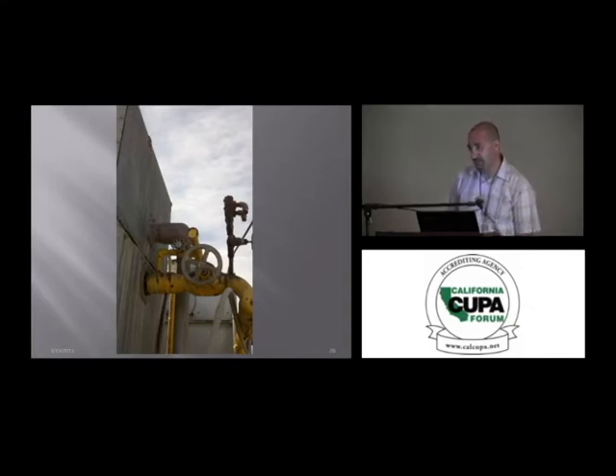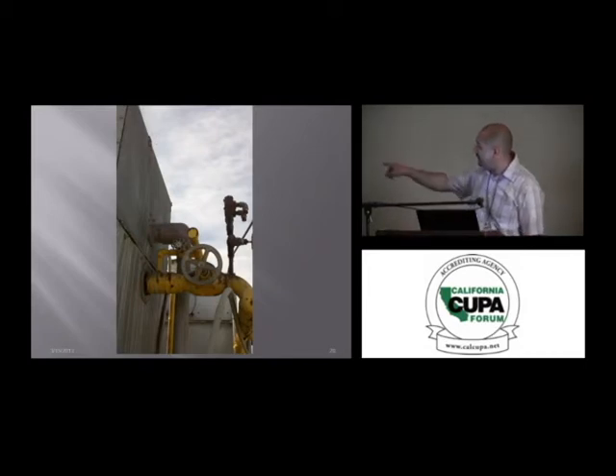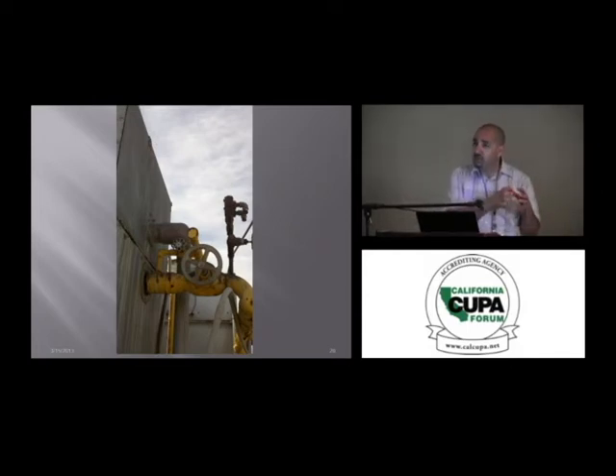Yeah, isolation valve, actually there's another thing. You see that big isolation valve coming off, that's a condenser, coming off the condenser. That relief valve, there are 2 more condensers there. And that relief valve, they didn't want to replace them. It was past their 5-year replacement period. And this facility right next door, I can throw a rock from this facility and hit a supermarket that's right next to it. Condensers have them right up on the isolation point, and they're there to relieve the condenser.